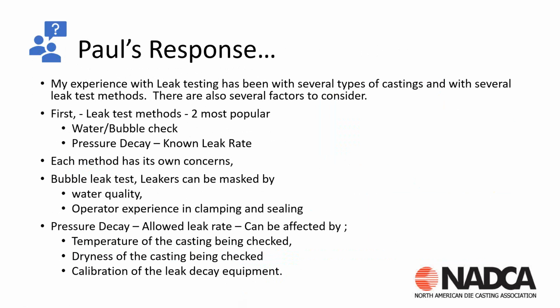Now, I've also done that same pressurization with helium, a much smaller molecule than air. So you can use air or you can use helium. When you pressurize those, you've got to make sure that you've got good protection for your employees in case the casting lets loose. But with the smaller molecule, you're going to see much higher leak rates. So helium versus air. So that's the water bubble check.